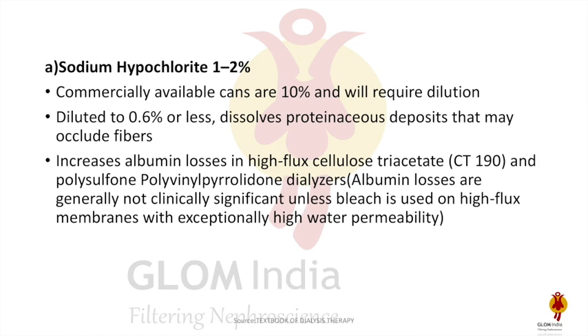The first agent is sodium hypochlorite. It is commercially available at 10% strength and needs to be diluted to 0.6% or less. It dissolves protein deposits that may occlude the fiber. One disadvantage is that it can increase albumin loss with reuse.